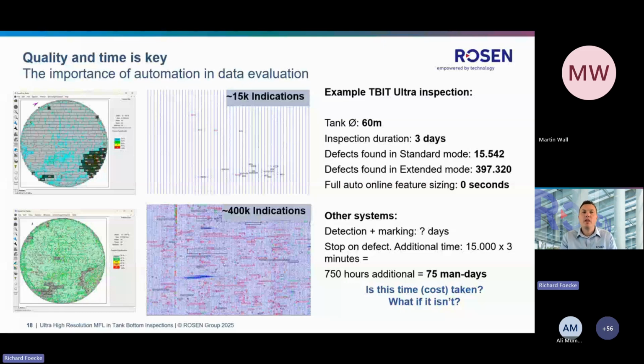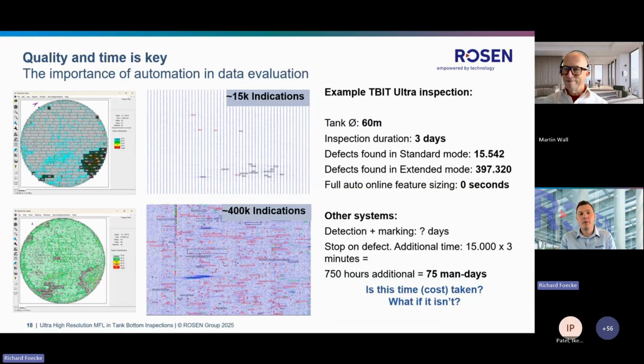Actually not, no. We have certain cleanliness requirements and we have them documented in a certain procedure or document. So there are certain things that need to be considered. Of course, the bottom should be free of dust and moisture. And typically bottoms are high water pressure cleaned. And there are also certain standards that you can apply for cleanliness. But to answer your question, there's no difference in cleanliness requirement between a standard and ultra service.